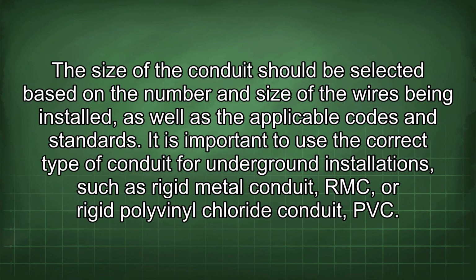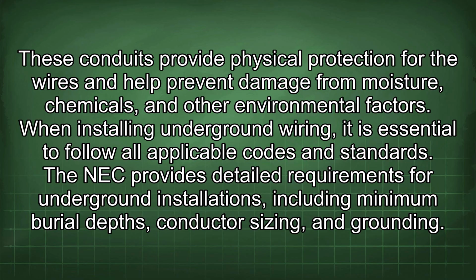The size of the conduit should be selected based on the number and size of the wires being installed, as well as the applicable codes and standards. It is important to use the correct type of conduit for underground installations, such as rigid metal conduit, RMC, or rigid polyvinyl chloride conduit, PVC. These conduits provide physical protection for the wires and help prevent damage from moisture, chemicals, and other environmental factors.